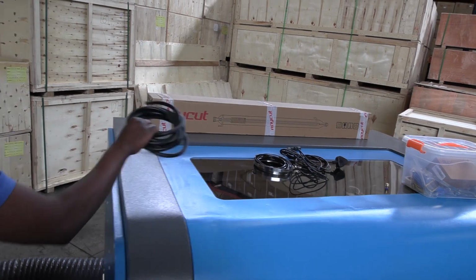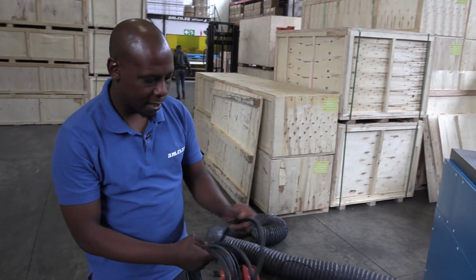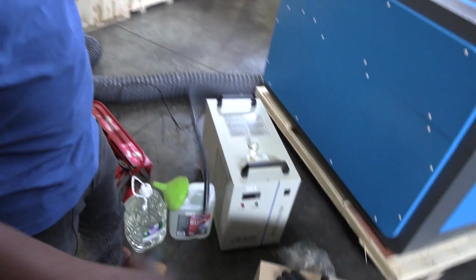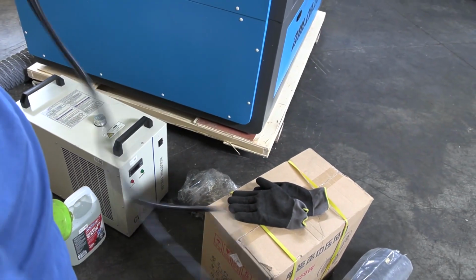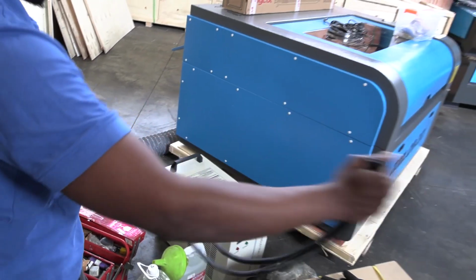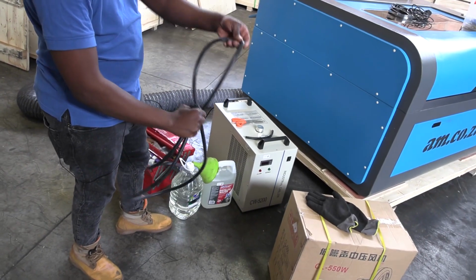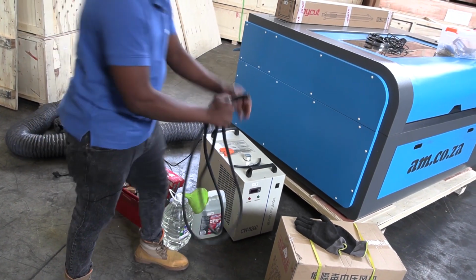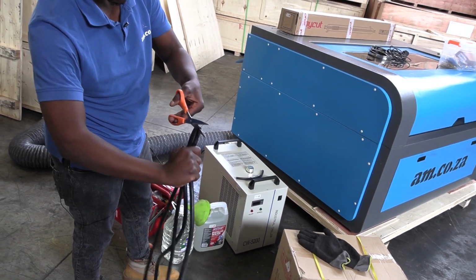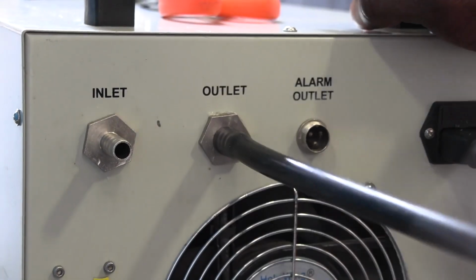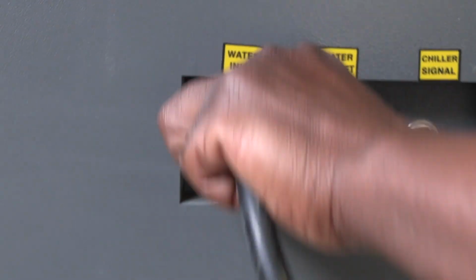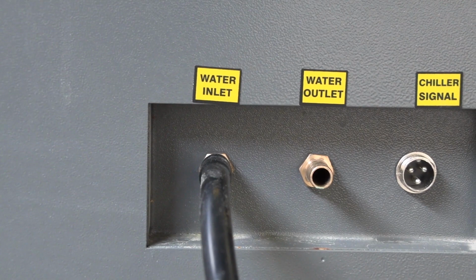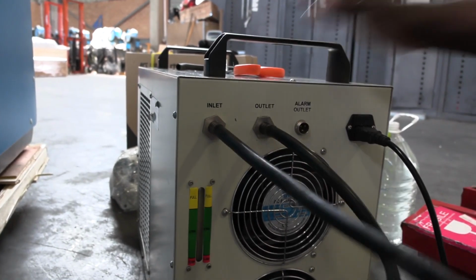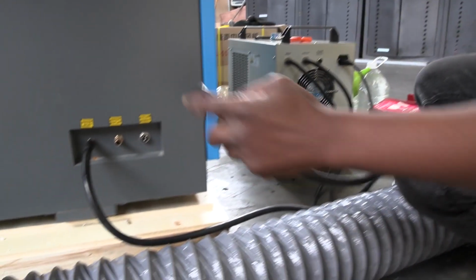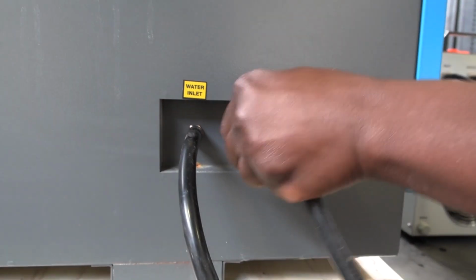Let's start off with installing our water chiller. So firstly, I would like to unroll the external water pipes, join these two together all the way to the end, and divide them equally into two. The outlet pipe on the chiller will connect into the water inlet pipe onto the machine. My inlet pipe onto the chiller will connect to my outlet pipe onto the machine.